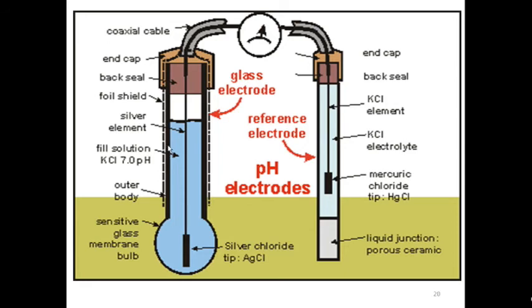The principle of the pH meter: it measures the electrochemical potential developed between the known liquid inside the glass electrode and the unknown liquid outside the glass electrode, because the thin glass bulb allows mainly small hydrogen ions to interact with the glass.